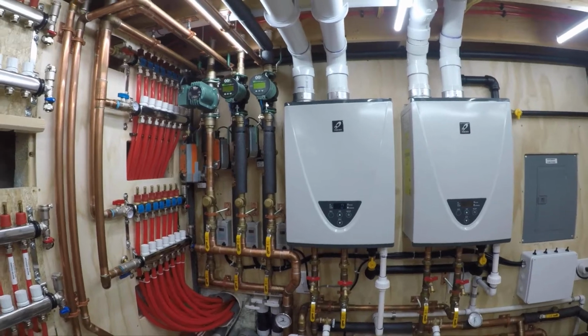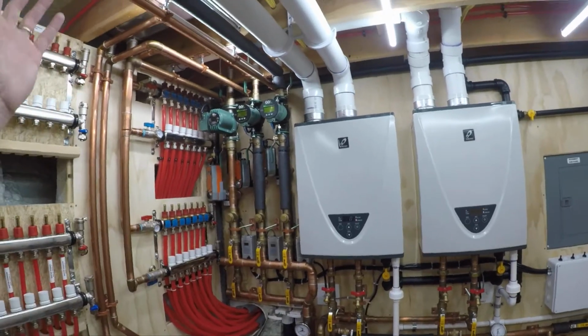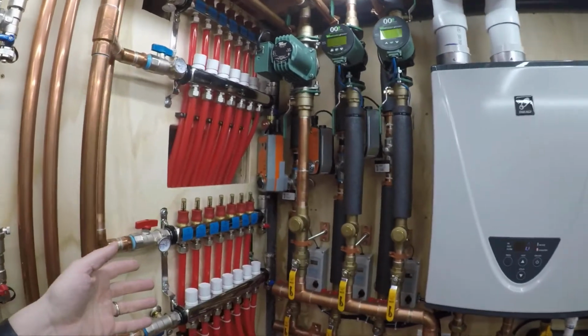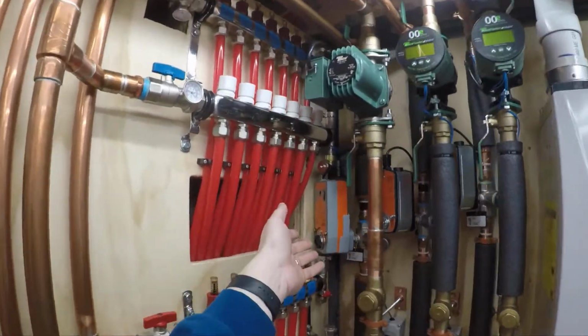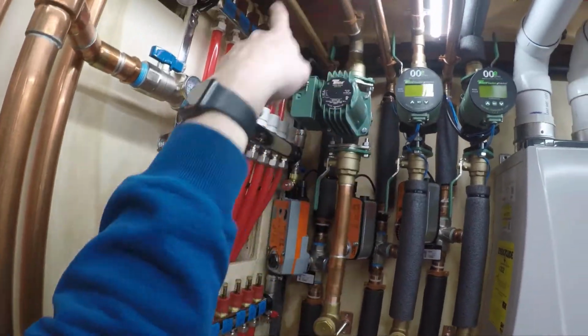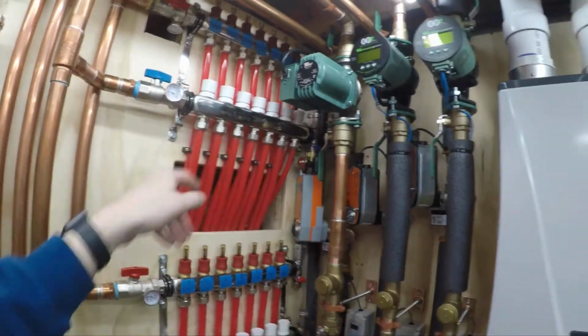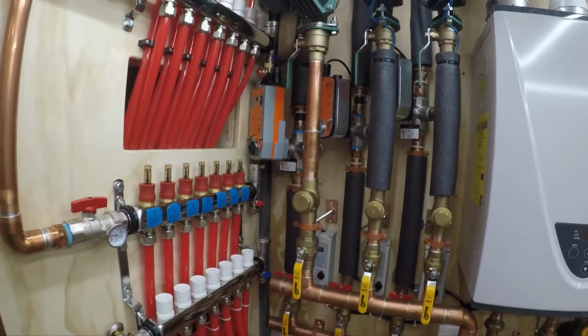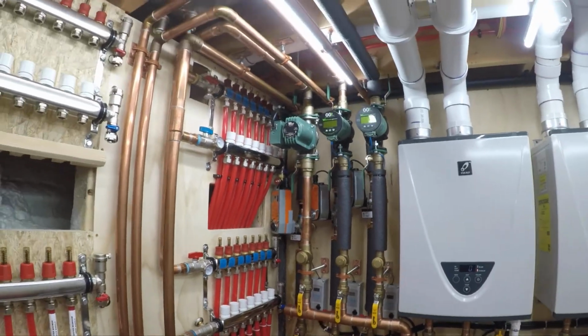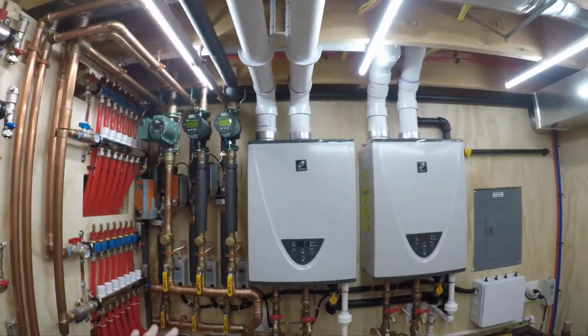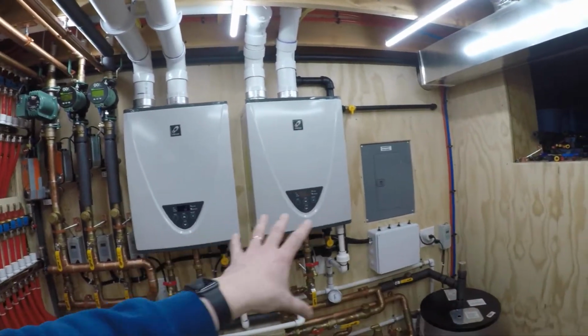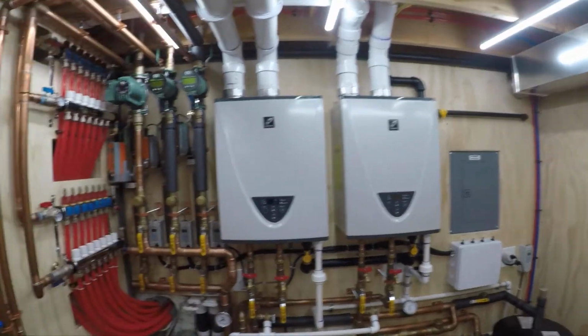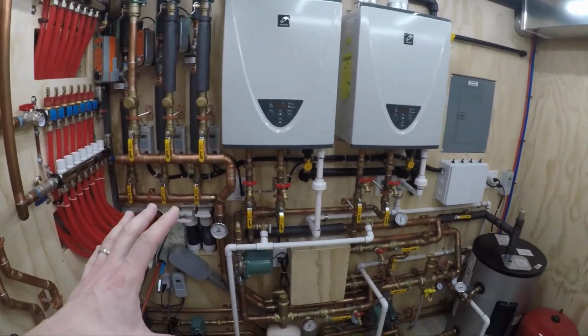It comes on, fires them up, adds more heat. Glycol comes back hot, aquastat's satisfied, three-way valve closes. Now the glycol is just circulating itself out through the loops, back, just keeps going, done. I'll do another video on the controls and the relays that are in there, and I'll show all that because this one's getting long. I just wanted to show you guys the piping on this one.